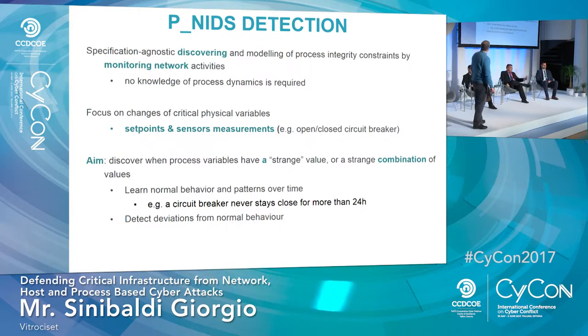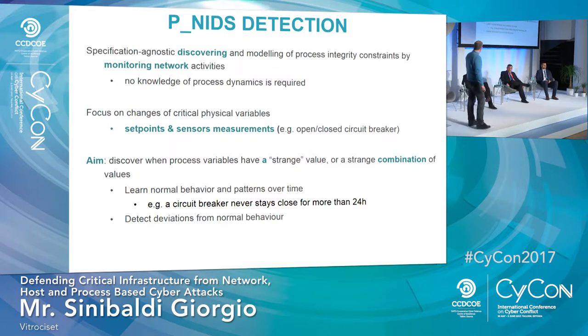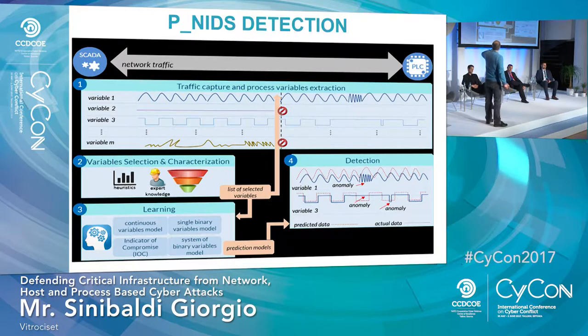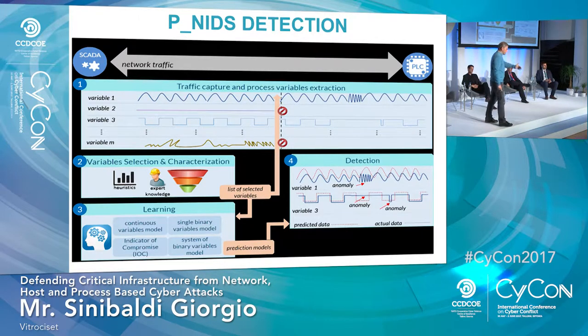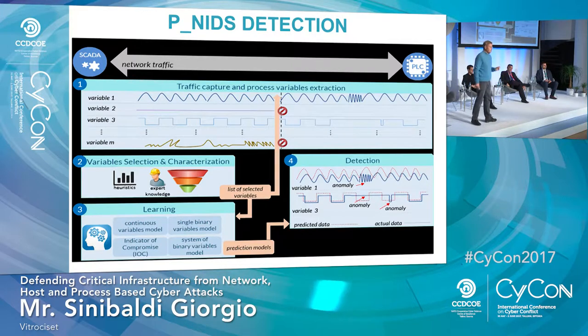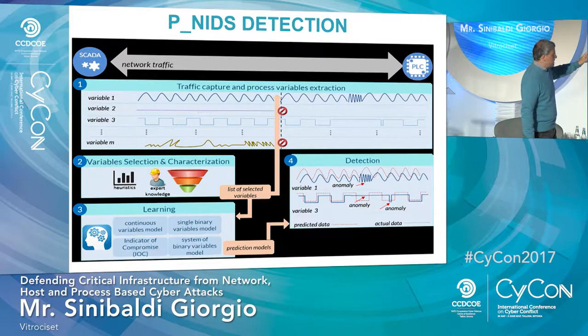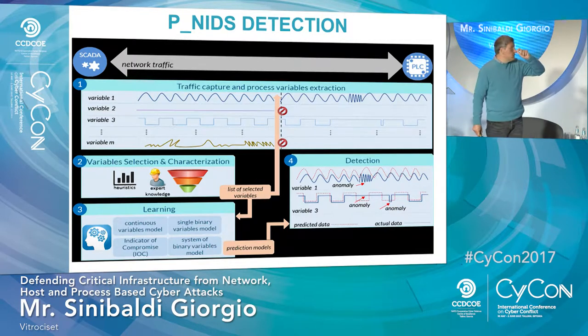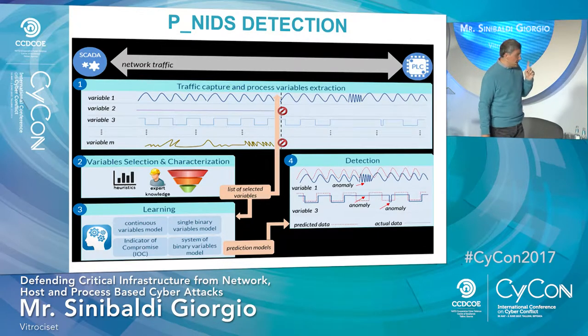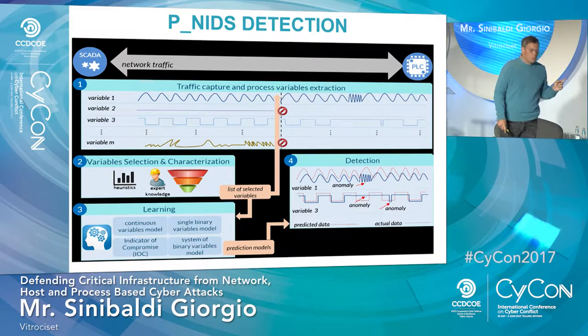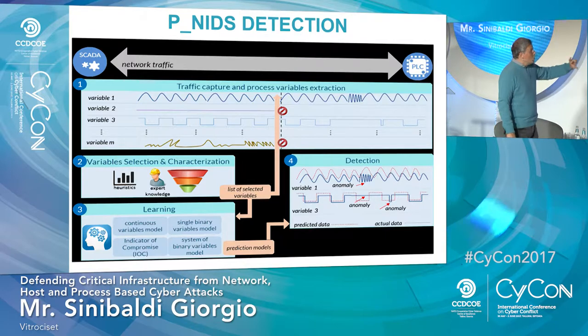Just to illustrate one tool: the P_NIDS detection tool makes an inspection of network activities. In the first step, we choose a series of variables running in the SCADA system. By step two, we analyze each variable to see if it is a command, a set point, or something important. We learn about this variable and make a prediction of what its value should be. If a variable differs from what we expect, we launch an alarm on the system.